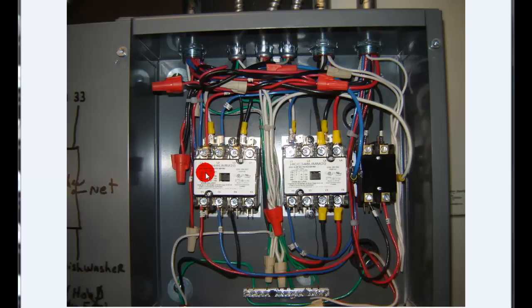This contactor right here operates the supply fan and the hood lights. So in case there's a fire and the fire suppression system is tripped, it'll open up the contacts and this contactor will open up and shut the power off to the exhaust fan and the, or I'm sorry, the make-up air and the lights.